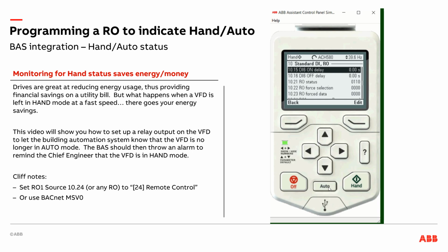So you probably can't quite hear my demo and the relay clicking in the background. But believe me, when I go from auto to hand and you see that 1 go to a 0, there's a click in my demo case right now. Let me know the relay is changing state. And you can see that right here in the relay output status. So if this relay output 1 was wired back to the building automation system, the BMS would know right now that it is in hand mode.